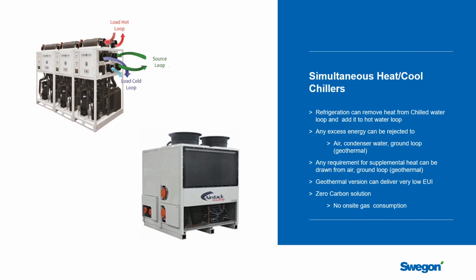And that means that you can move heat from the core of your building where your chill beams are running and cooling, and they're going to add heat to the chilled water loop. It gets back to the chiller plant, we are going to shift that heat into the hot water loop and use it on the perimeter chill beams, which could easily be in heating mode because of the skin loss through the building. And so this HVAC system will allow you to move energy from where there's a surplus of it in the building to where there is a need for it in the building. That's incredibly energy efficient, and we did it without having to burn any natural gas on the job site.